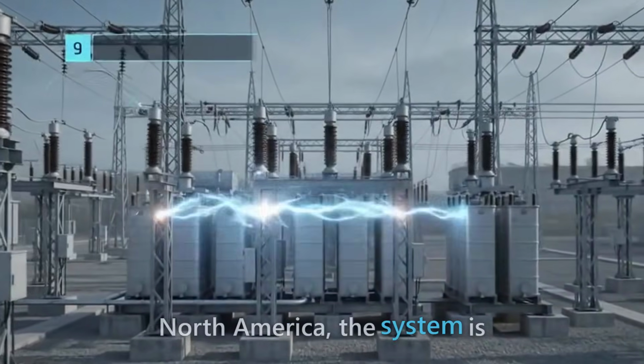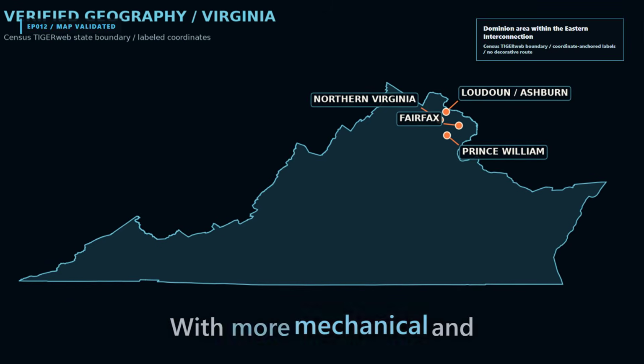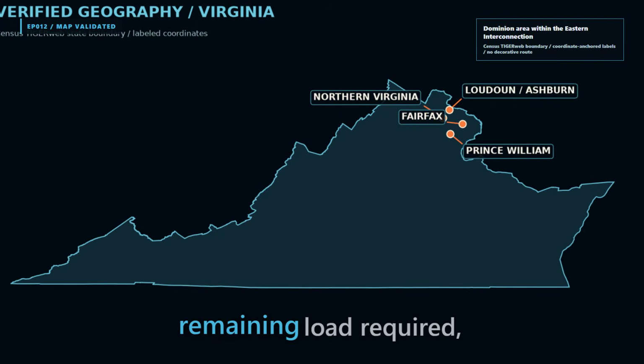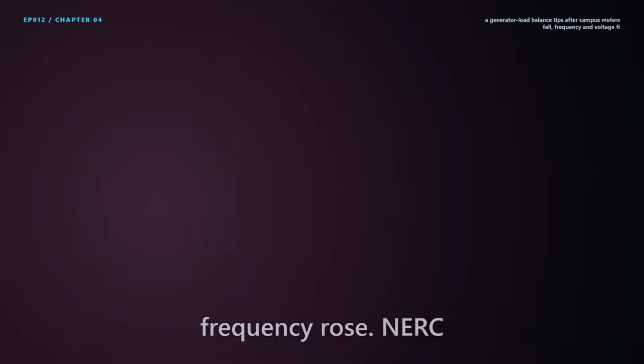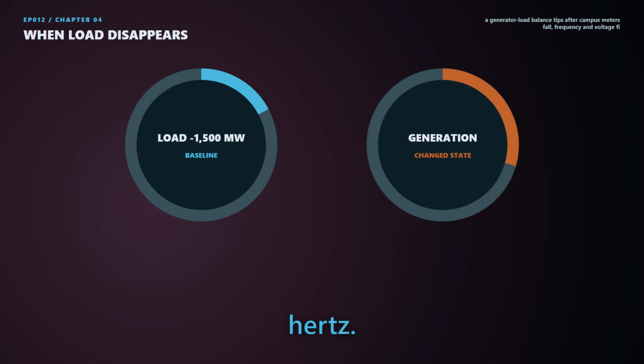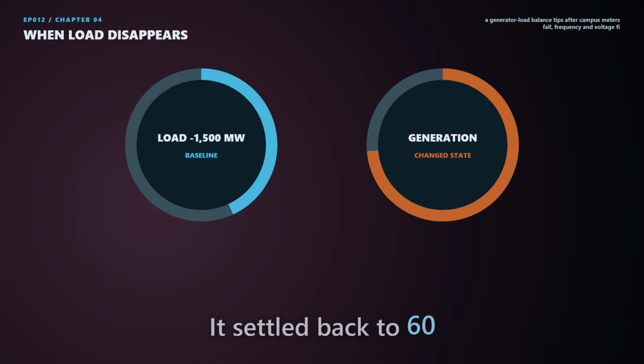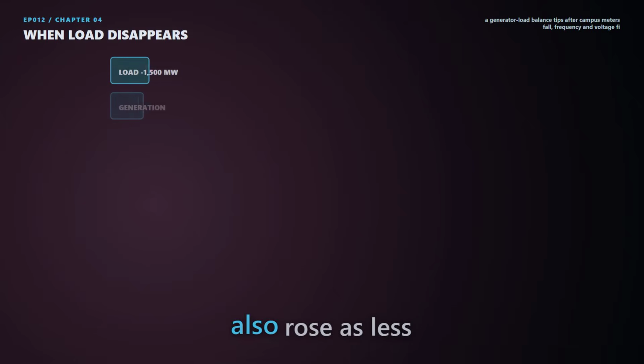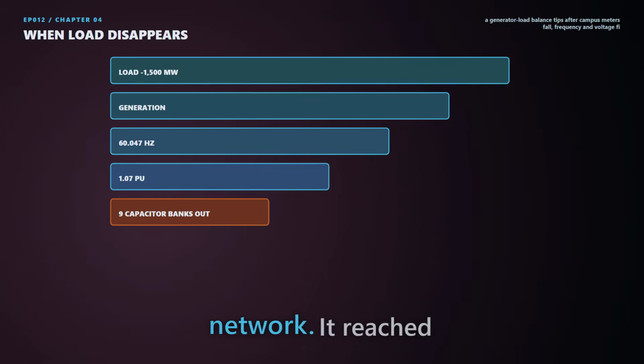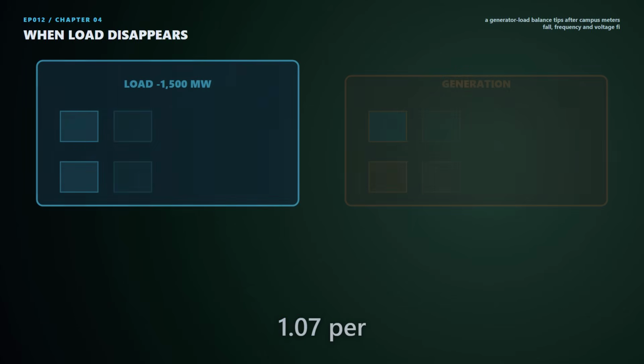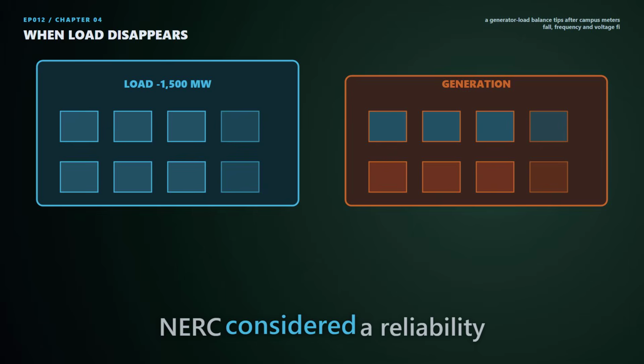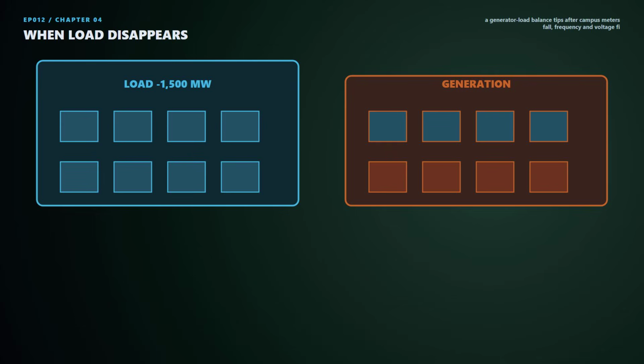In North America, the system is centered on 60 Hz. With more mechanical and electrical input than the remaining load required, frequency rose. NERC recorded a peak of 60.047 Hz. It settled back to 60 in about 4 minutes. Voltage also rose as less power flowed through the local network. It reached 1.07 per unit, below the level NERC considered a reliability risk in this event, but high enough to require operator action.